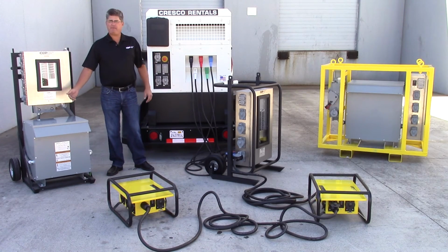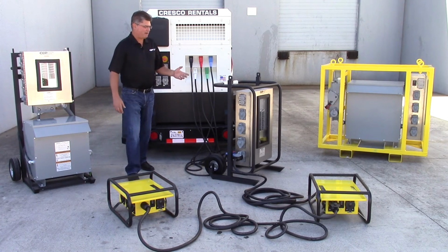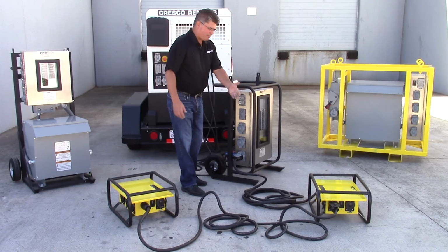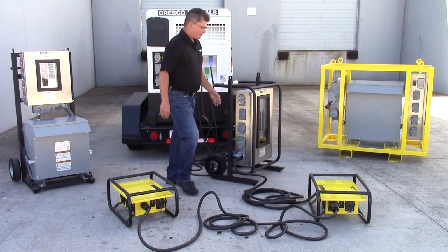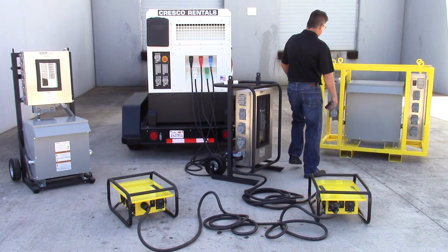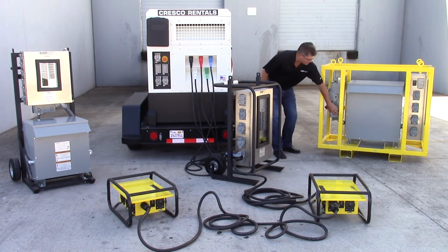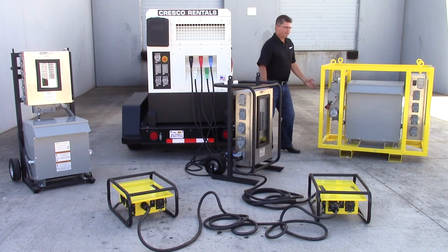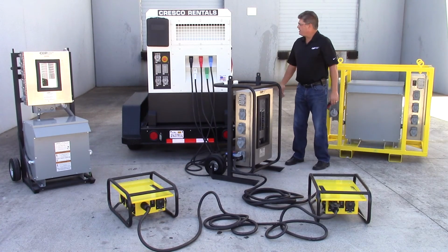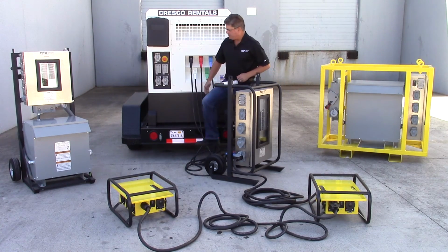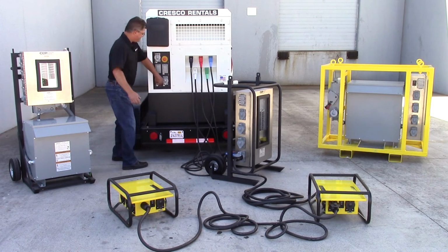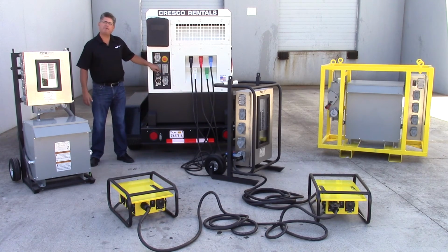Once the power is stepped down, now we have the 120/208 power necessary to be able to power the spider boxes or other equipment. Over here, you'll notice that this particular unit has a secondary disconnect on it, which we actually put on for welding applications. Happens to be a very popular accessory that we put on many of our units.